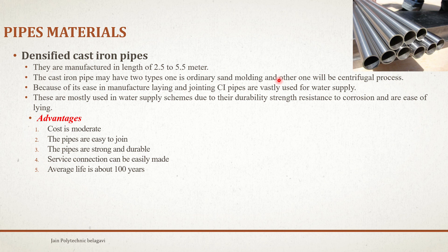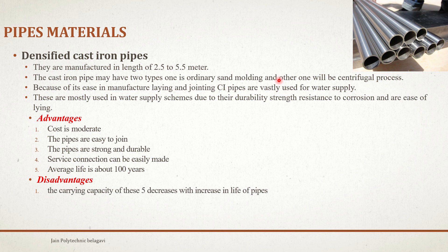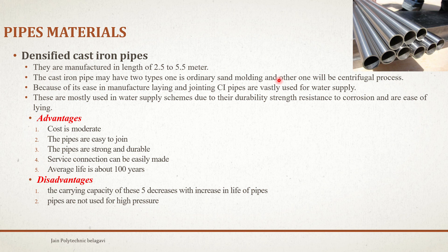Some disadvantages of CI pipes: the carrying capacity of these pipes decreases with increase in the life of the pipes, because of scaling caused by hard water. They are not suitable for high pressure — if any significant pressure is created in the pipe, it may develop cracks or even burst.